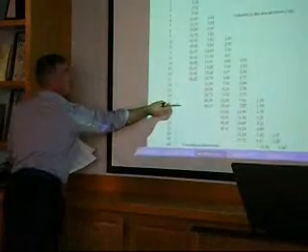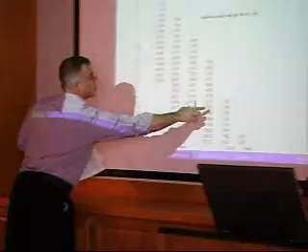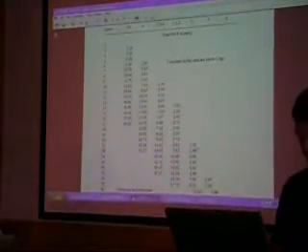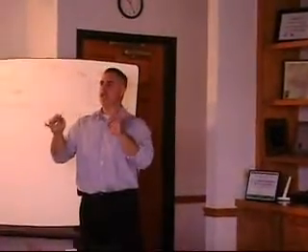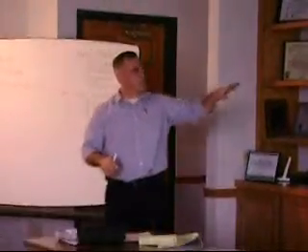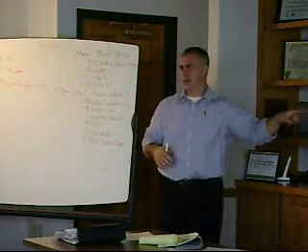Look at this column right here, this row right here. 1.5 pipe, 2-inch pipe. There you go. What that means is this: this 7.78 is how many feet of friction loss per 100 feet of pipe. You got 200 feet of pipe, you almost got 16 foot of friction.